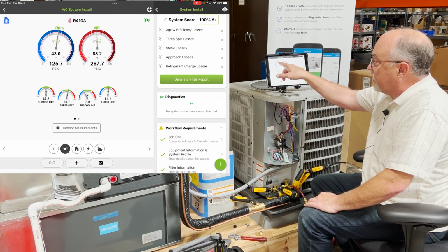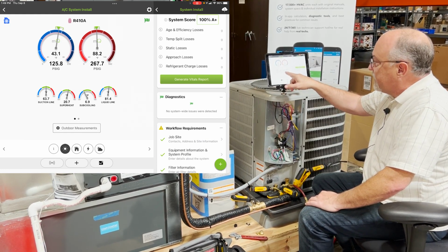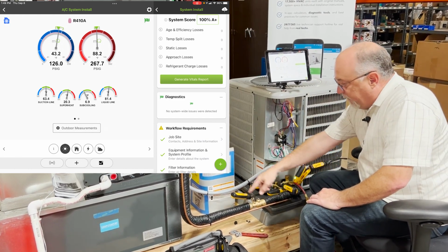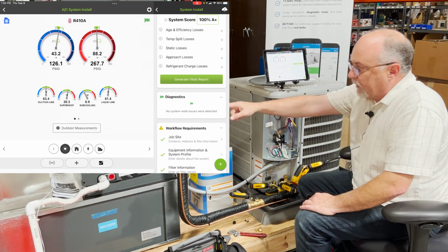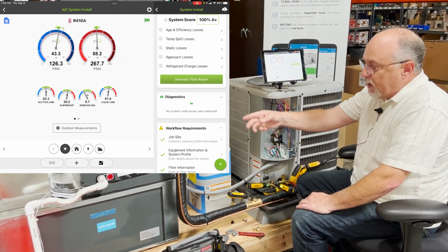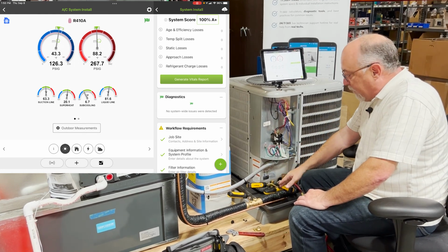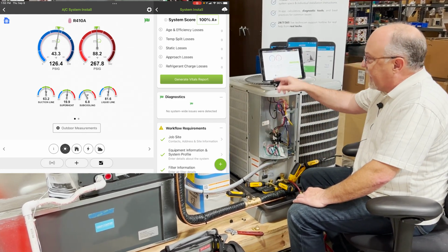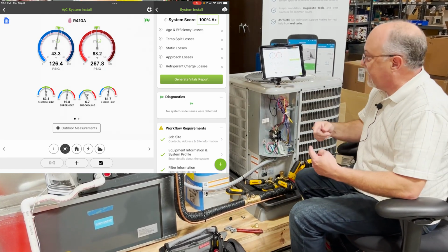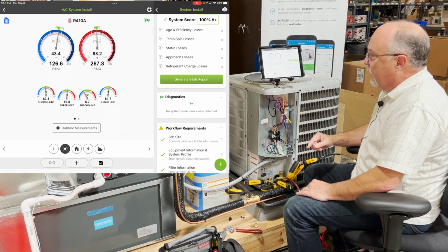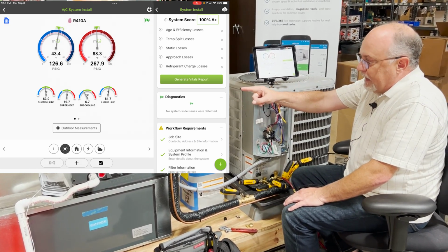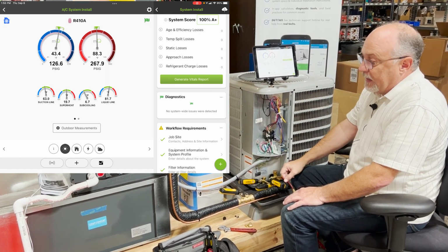We have no change in suction pressure here, but we are seeing our subcooling drop, and that's because overall we're continuing to feed the same amount of liquid into the coil, but we're not quite pulling the mass flow back the same. So even though the pressure's still up a little bit, we're not pulling the refrigerant back at the same rate, and it's actually stacking up inside of that evaporator coil. It's almost acting like a second condenser. And what's going to happen over time is as we stack more and more liquid in here, that is actually going to become a secondary condenser in some respects.